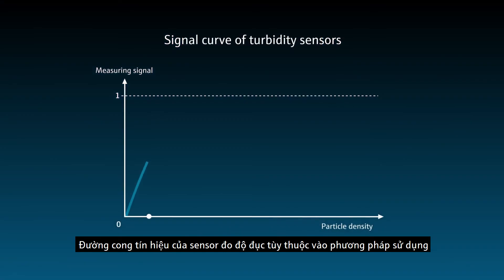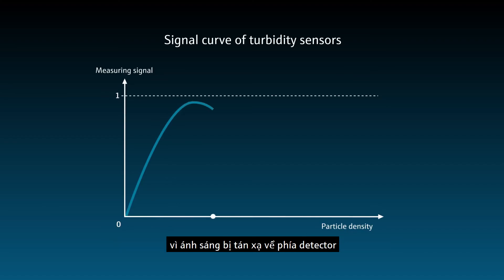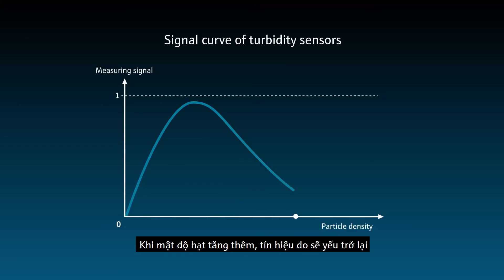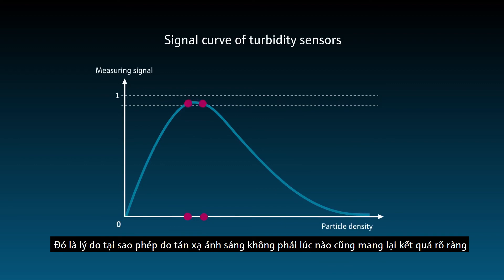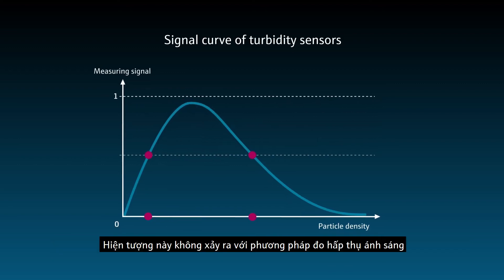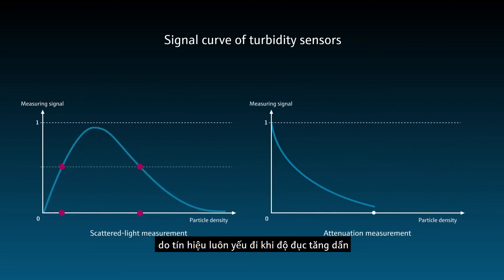The signal curve of turbidity sensors depends on the method used. With scattered light measurement, the signal curve rises up to a certain particle density because the light is scattered towards the detector. When particle density increases further, the measuring signal weakens again because the light is scattered so strongly that radiation no longer reaches the detector. This means scattered light measurement does not always deliver clear results. This phenomenon does not occur with attenuation measurement, where the signal consistently weakens with increasing turbidity.